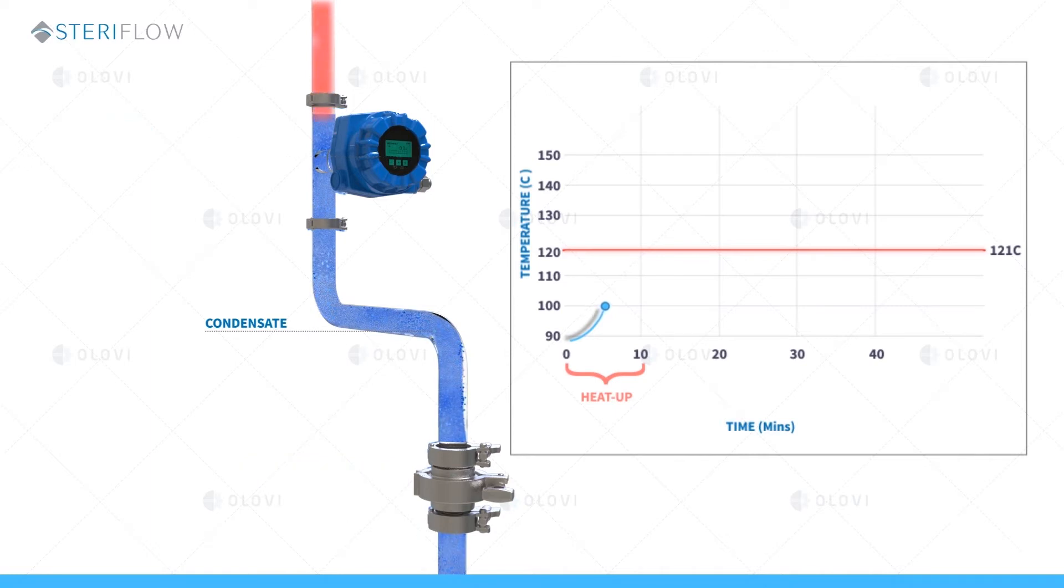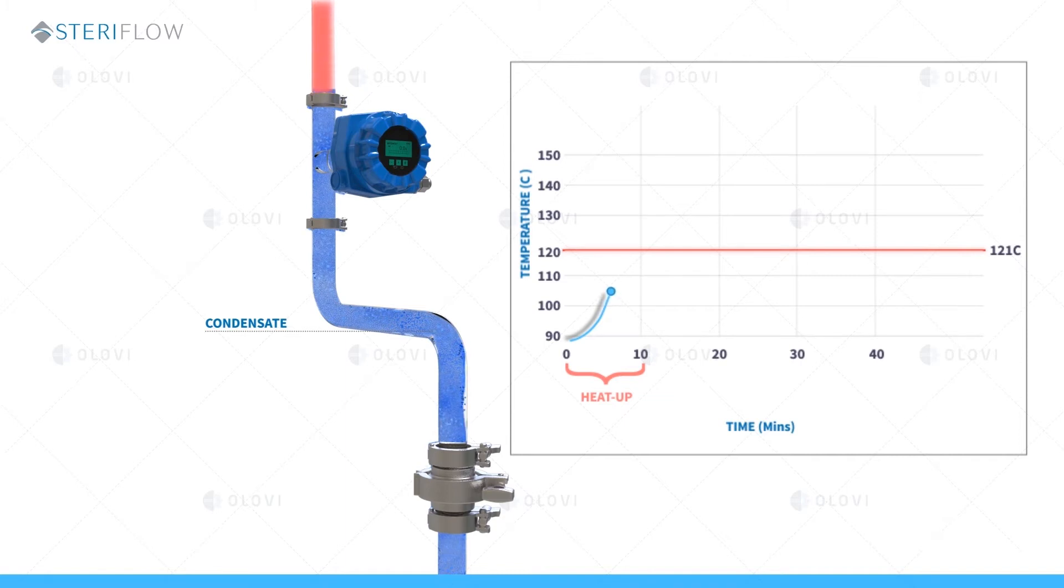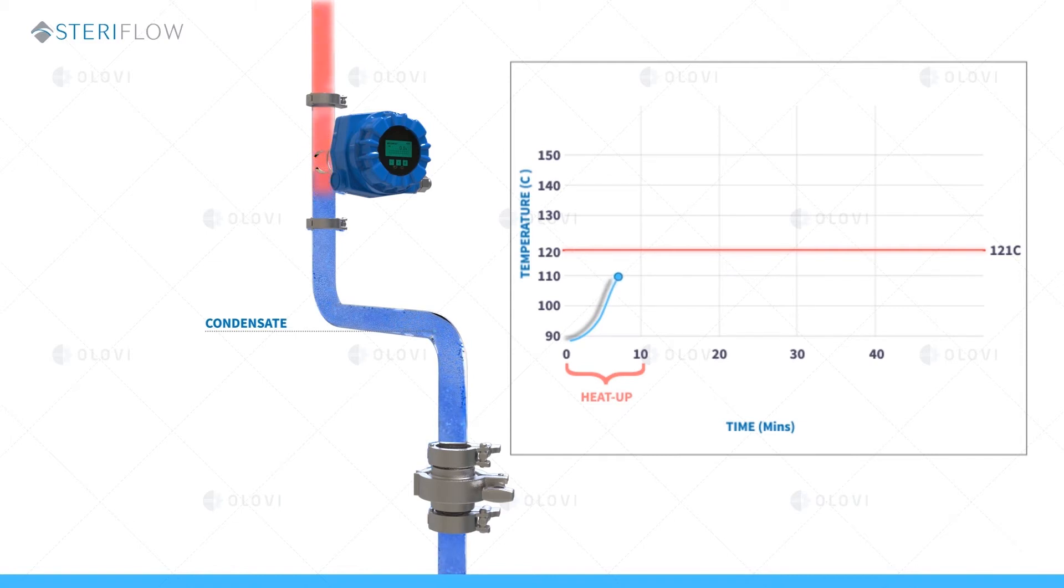It's not unusual for heat up condensate loads to back up to a level at or above the temperature validation sensor. As the system heats up closer to 121C, less steam is required and the amount of condensate produced lessens.